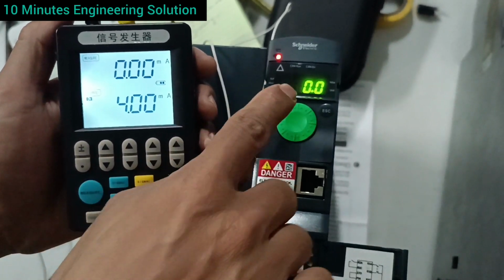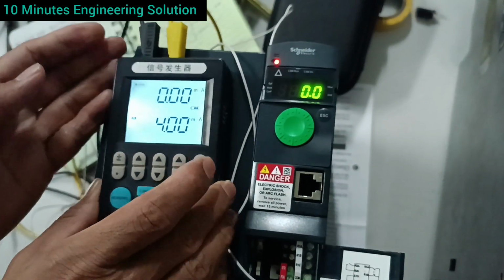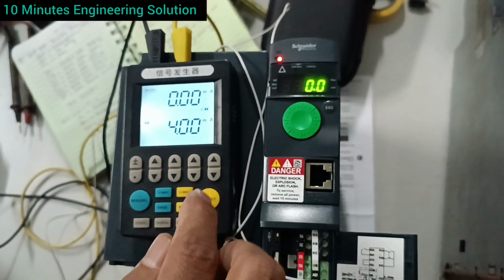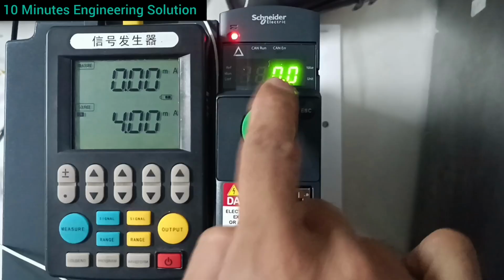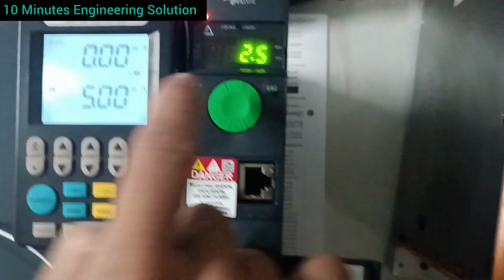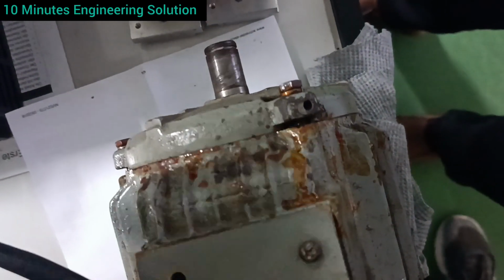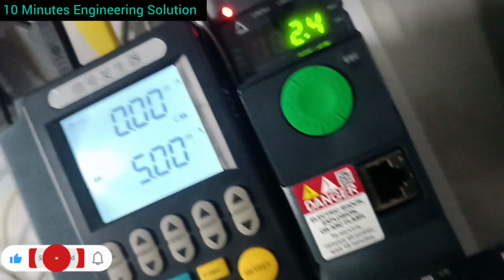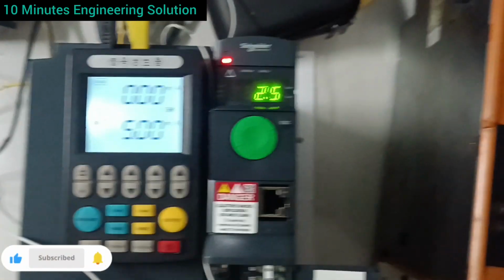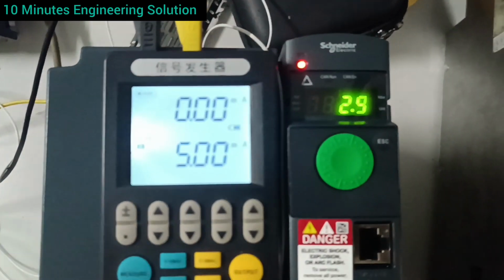You can see at 4 milliamps the VFD's value is 0, because of how I set CRL3. When I increase the milliampere, the VFD hertz increases and the motor also runs. You can see the picture here. I increase from 4 milliampere to 5 milliampere. Now VFD is 2.5 hertz.